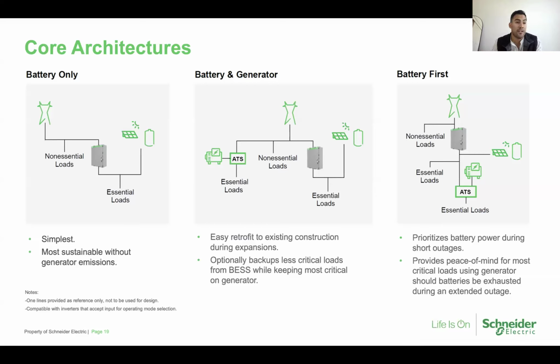And that's really the tricky part here of these energy storage systems: how you design your system so that it acts as a load during grid-tied operations, but you can disconnect that load and make it a power source to really power just those essential loads. And as you know, energy storage systems are sized for 3 to 4 hours of runtime on average, depending on the chemistry of the energy storage system. You can get longer runtime out of them. But mainly for the National Electric Code, you need at least 2 hours. On top of that, the more batteries you add, the longer the runtime, but it's something to consider. And this battery only architecture is the simplest, most sustainable here. You don't have a generator, and if you have a solar system there, you use it to charge that battery energy storage system, or if not, you discharge at one time, or when you lose power, and when rates are normally high.